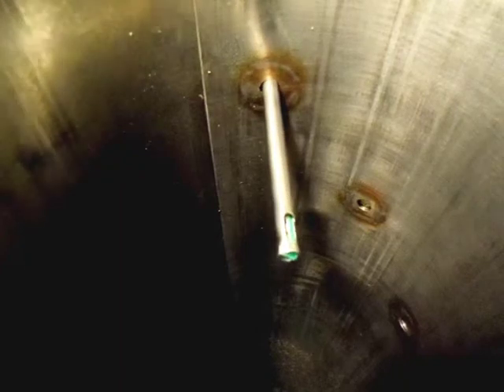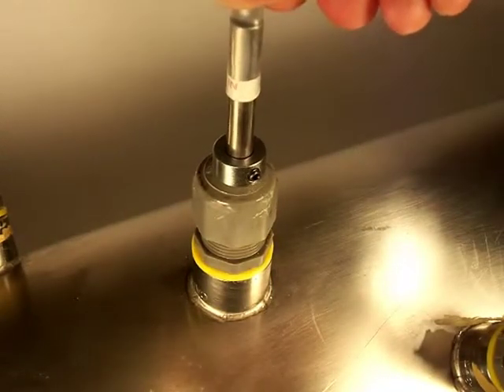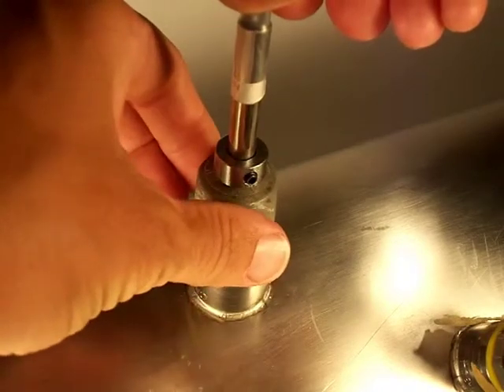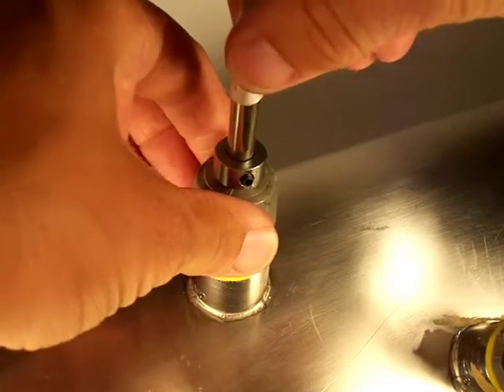After the probe has been positioned in the air stream correctly, securely tighten the compression fitting to prevent the air from leaking out of the duct system between the fitting and the probe. Try to prevent the probe from changing its position significantly as the fitting is tightened. Failure to install the probe properly will result in an inaccurate reading of the airflow rate.